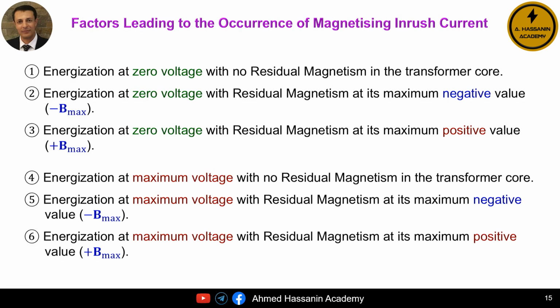3. Energizing when the voltage is 0 and there is residual magnetism in the iron core at its maximum positive value. 4. Energizing at maximum voltage with no residual magnetism in the iron core. 5. Energizing at maximum voltage with residual magnetism in the iron core at its maximum negative value. 6. Energizing at maximum voltage with residual magnetism in the iron core at its maximum positive value.